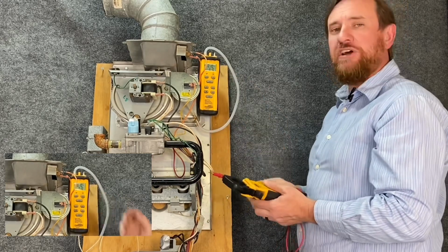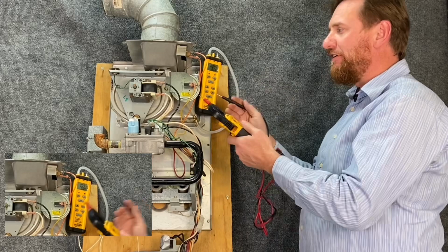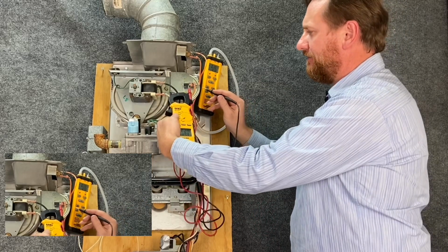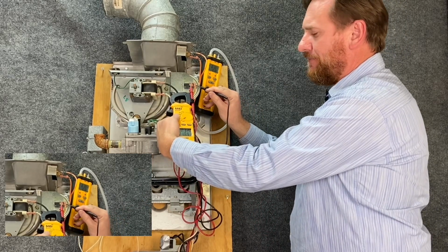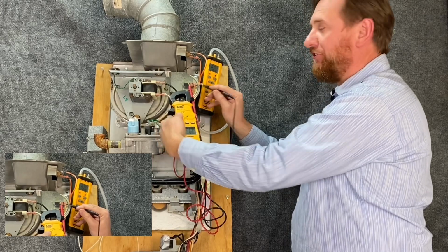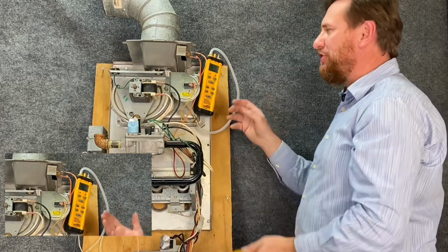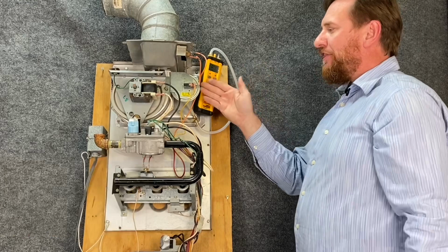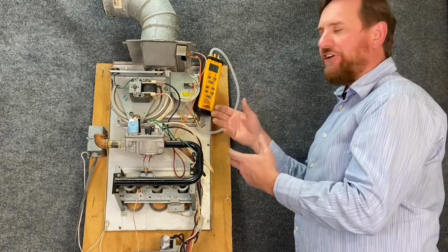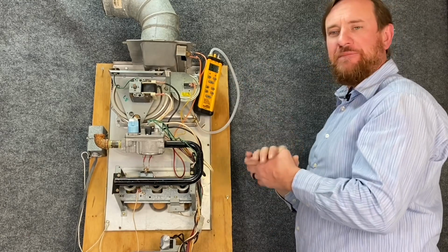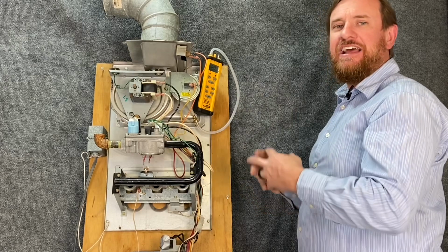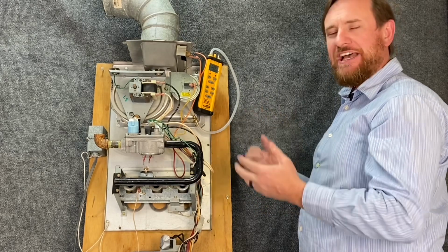So the switch right now is not going to close because I do not have enough vacuum going to it. At 0.10, the switch should be open, which means I should read voltage. Let's check. I'm reading 27 volts, so I know my switch is open, and it should be open. You could think, well, the switch isn't closing and I want it to close, let's replace the switch. That would be wrong. That's like saying your gas gauge is on E, I need to get a new gas gauge. Do you have gas in the car?